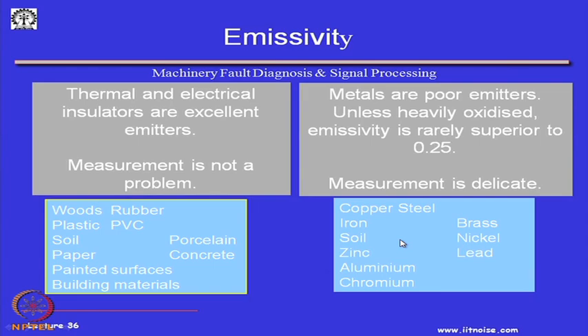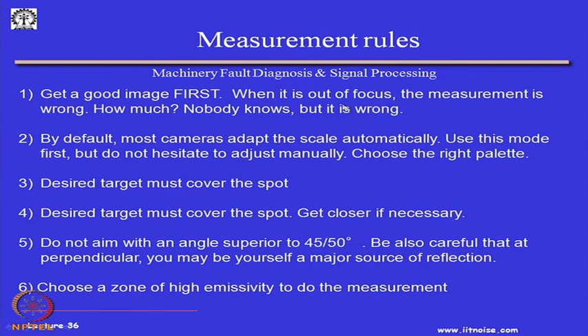Now, how do I know, while doing calibration, that I am doing the right kind of measurement? So, typically people follow some rules, but a good thermal imaging procedure requires that I first capture a good image. When it is out of focus, the measurement is wrong. How much? Nobody knows, but it is wrong. So, the first thing is we have to focus it.